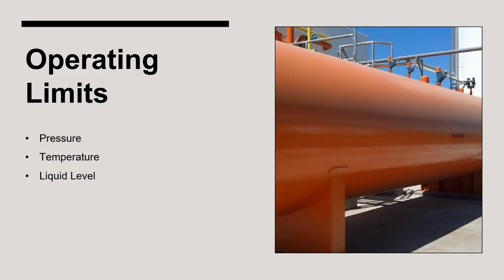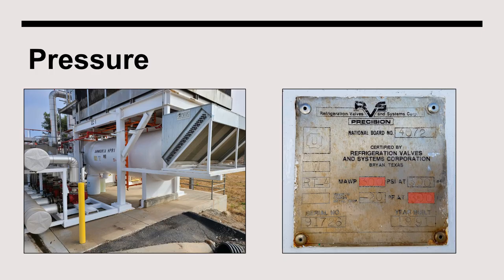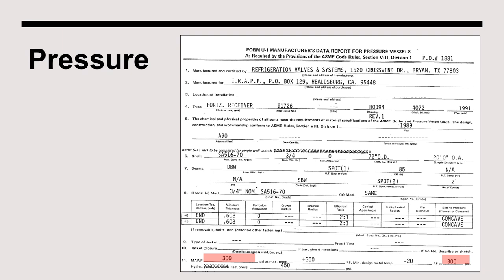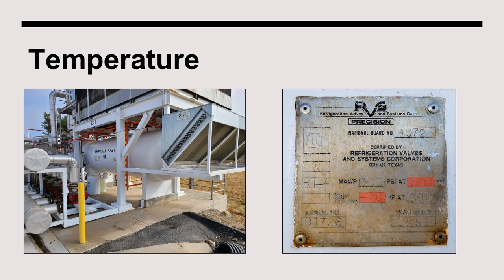The three most relevant operating limits for high pressure receivers are pressure, temperature, and liquid level. The maximum allowable working pressure of a high pressure receiver will be displayed on the ASME nameplate, and under no circumstance can the pressure inside the vessel exceed this value. The MAWP can also be found on the Manufacturer Data Report, or U1 form. Similarly, the vessel cannot operate beyond the temperatures displayed on the nameplate — in this instance, the vessel can safely operate below 300 PSI at temperatures between minus 20 and 300 degrees Fahrenheit.